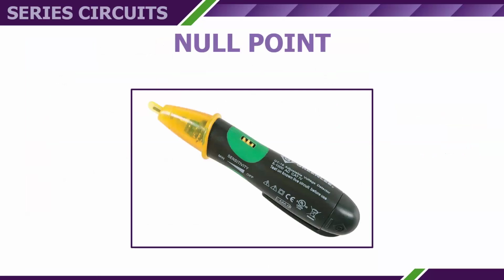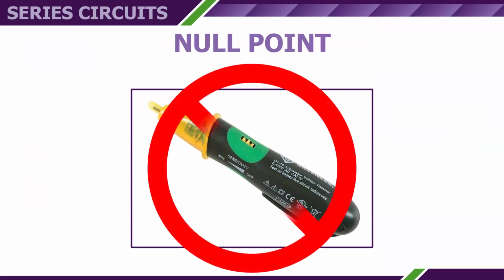Tick tracers, you've heard them called voltage sticks, pocket testers, and so on. They work great on a voltage circuit. It could be deadly on an Airfield lighting circuit. Do not use it on an Airfield lighting circuit. Our Airfield lighting circuits are ungrounded. This device, in order to work properly, relies on the capacitance between the device, the person holding it, and the earth. It requires some current flow, although it may be very low.